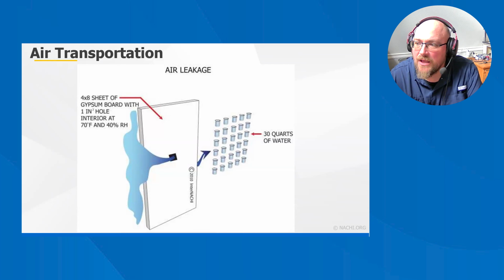Relative humidity, often referred to as RH, refers to the amount of moisture contained in a quantity of air compared to the maximum amount of moisture the air could hold at the same temperature. As air warms, its ability to hold water vapor increases. This capacity decreases as air cools. For example, according to the psychrometric chart, air at 68 degrees Fahrenheit with 0.216 ounces of water per pound of air versus the same air at 59 degrees Fahrenheit holds about 28% more moisture.